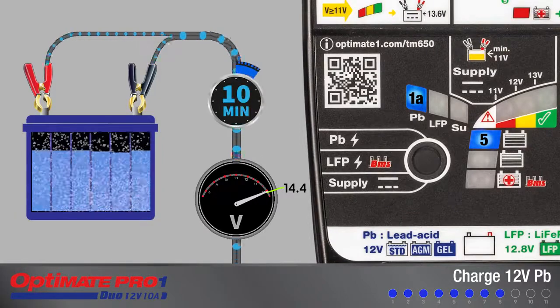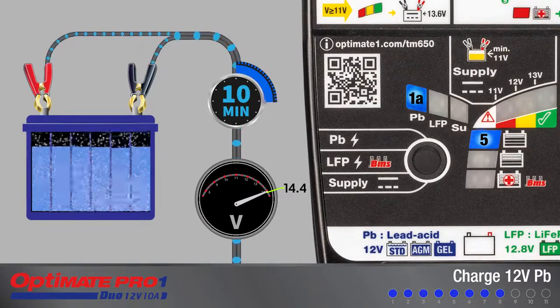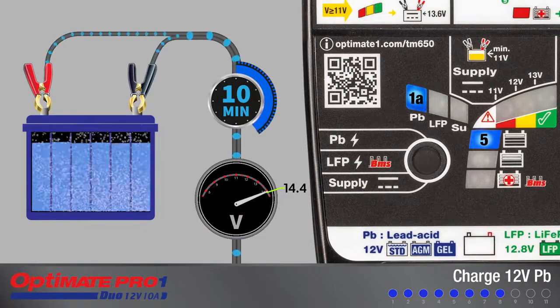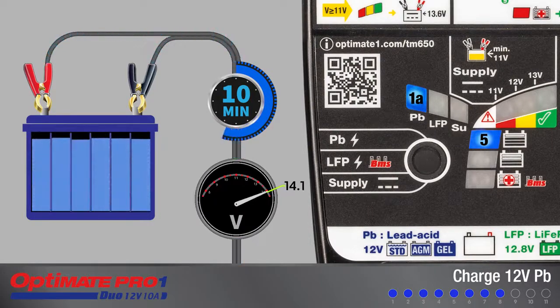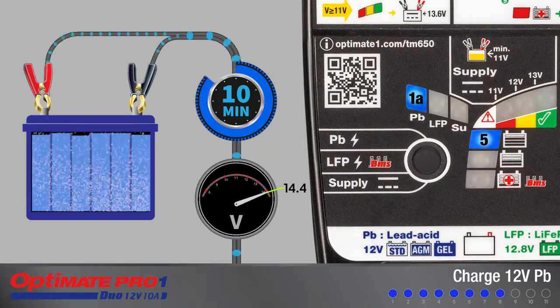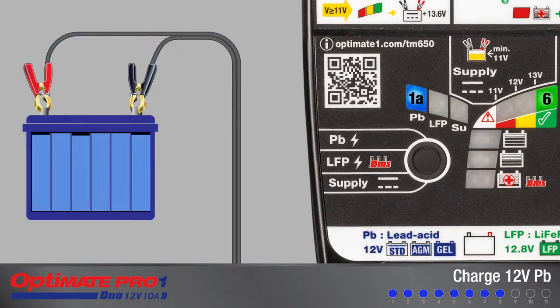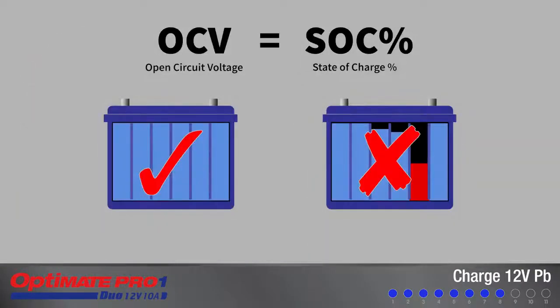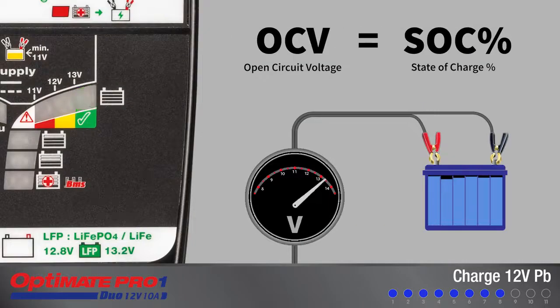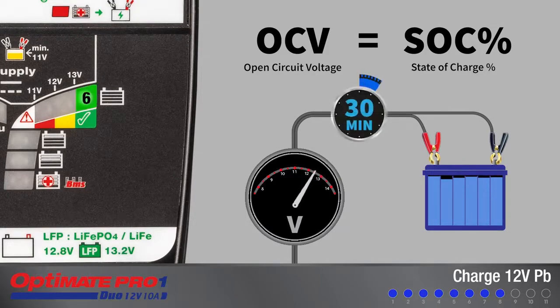After this, the AmpMatic current control program delivers pulses of current for a period of 10 minutes, with voltage cycling between 14.1 and 14.4 volts to equalize the individual cells within the battery. Charging has been completed when LED 6 is flashing. A state of charge test is conducted to determine the serviceability of the battery. The open circuit voltage of a battery is directly proportional to its state of charge percentage after it has been allowed to settle for 30 minutes or more.